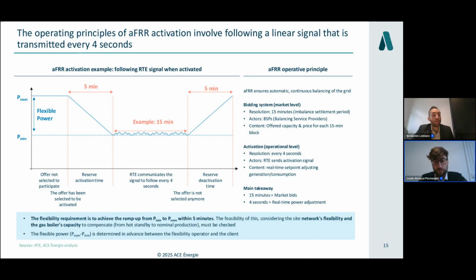So if you want to go toward that direction with a hybridization project and an e-boiler, you have to check the flexibility requirements to achieve this ramp up from minimal power to nominal power within the 5 minutes. You have to consider the network feasibility, also the gas boiler's capacity to compensate, because if you reduce the electricity consumption of the e-boiler, you have to compensate with the gas boiler during the same period of time to get the steam production you need.